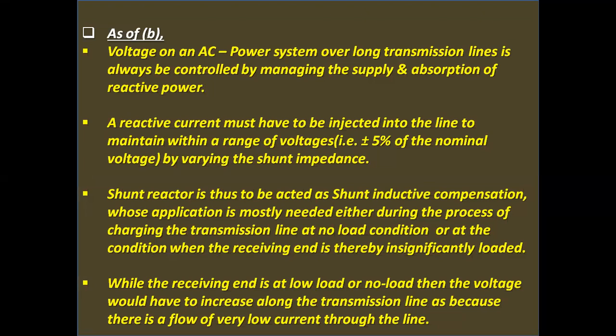A shunt reactor is thus to be added as shunt inductive compensation, whose application is mostly needed either during the process of charging the transmission line at no load condition, or when the receiving end is insignificantly loaded, that is lightly loaded, while the receiving end is at low load or no load. Then the voltage would increase along the transmission line, because there is a flow of very low current through the line.